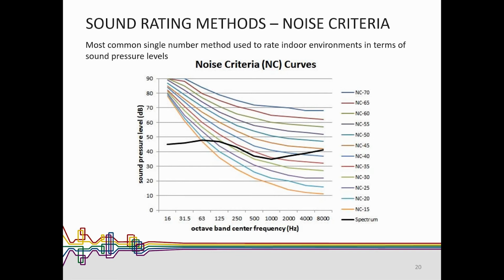Based on those frequencies. Now, what does that tell us? It tells us that if we want to improve this space by a substantial amount, say get down to NC 35, we could dampen all the frequencies from 1,000 hertz up, and we would achieve that. We don't really have to worry about any of the low frequency stuff at all. We just have to worry about the high frequency stuff. So that's usually good for mechanical engineers because some of our stuff tends to be loud and thumpy. And we can just get rid of the hissy stuff, which is a lot of times electronics anyway. So we can blame the electrical engineers for that. So this is the common way.